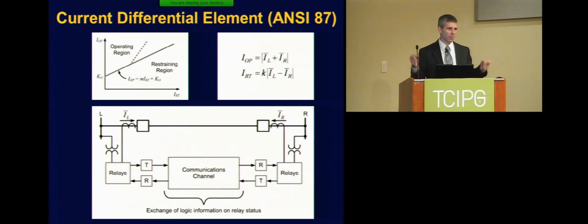The challenge is you need to be able to share that current differential information from one end of the line to the other. That's when we started introducing communications into certainly the protection side of things. And it's a great benefit. It gives me total protection on the entire line. However, I have now introduced the communication channel, and the communication channel can fail.